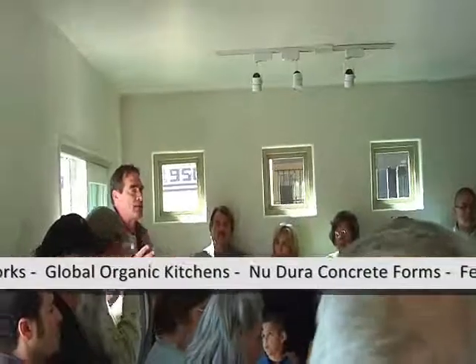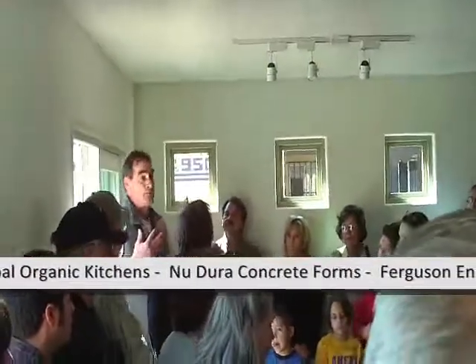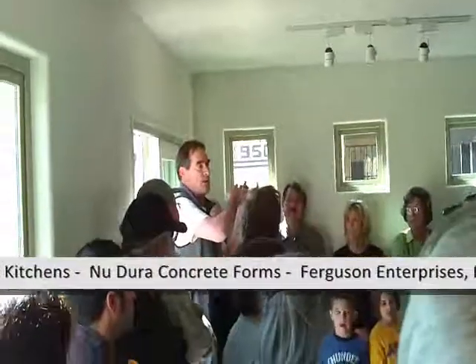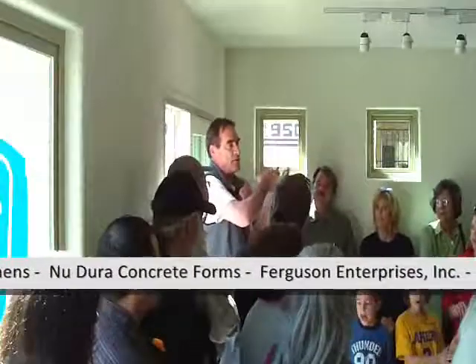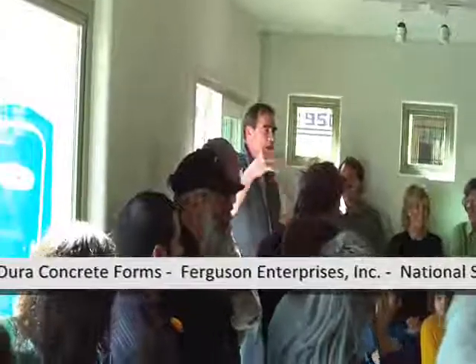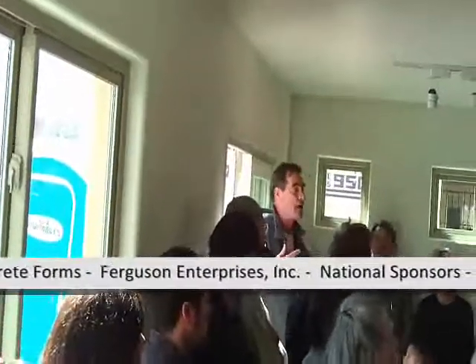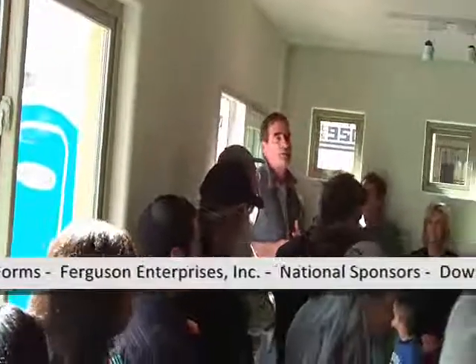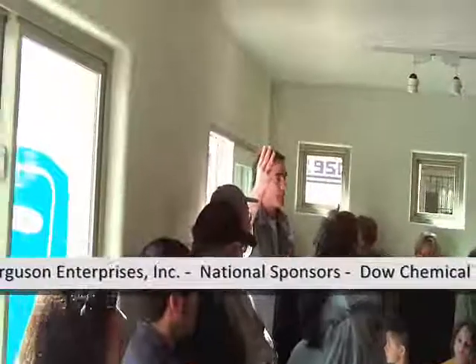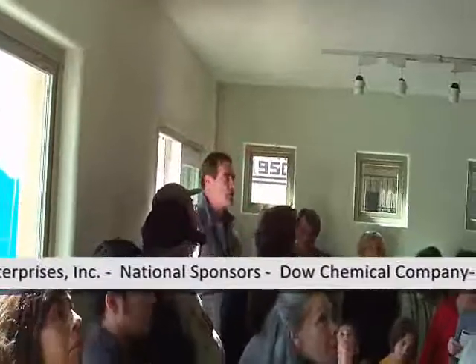The rules basically say that you should have all fresh air in your house about every 3 hours. The house next door, built probably maybe 100 years ago, 80 years ago, is getting probably fresh air about every half hour. This house, at 0.1, would only get fresh air naturally about every 10 hours. That's too tight. That's why the HRV is part of the program here. We also will have compact fluorescent light bulbs in all the house, and the light fixtures.